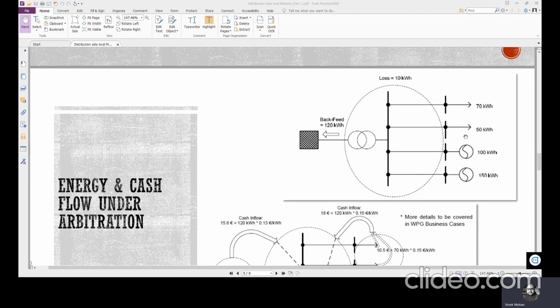So locally, this 120 is fed from these two local generators. So 250 minus 120 is 130. So the excess energy 130 can be pumped to the grid. But the loss in the local system is 10 kilowatt hour. So 120 can be pumped to the grid or backfed to the grid. So this is known as the backfeeding capability of the microgrid.